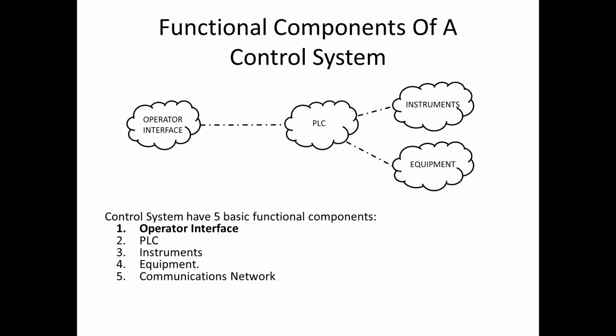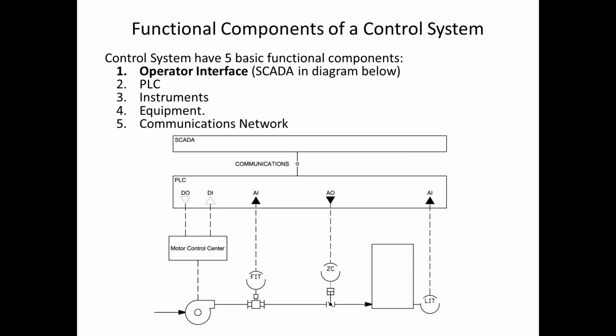So a good example would be that you have a tank that normally fills up, and when the level gets down, the transfer pump turns on and fills the tank up. Maybe you want to, for some reason, take that tank offline. So you can take manual control of that piece of equipment to prevent the transfer pump from filling the tank back up, and then you can take local control of the metering pump and allow that metering pump to bring that level down, so that when you take that piece of equipment offline, you have an empty tank. That's outside of the normal operation of the PLC, and that's something that an operator can come in and take local control of. So we'll talk a little bit about that.